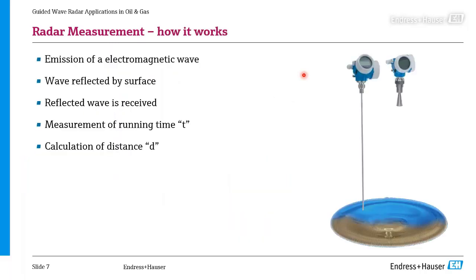Let's have a very easy overview of how it works. So we have here our guided wave radar and our free space radar, and from this we emit an electromagnetic wave down to the surface of your water or your oil. And as soon as this electromagnetic wave hits the surface, there is a change in the dielectric constant. Because the dielectric constant, for example, for air is typically 1, for water it's around 80. And we need this change because this change will then reflect the electromagnetic wave back from the surface up again to the device.